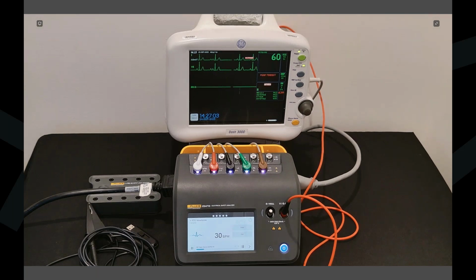One of the really cool features about doing this, if you wanted to set your limits, you could set a normal limit, a lower limit to set the alarms off on your monitor. You could reset it back to a normalized limit and then reset it back up to your high limits, capturing a full spectrum of testing all within one procedure. So here I see two things. I see my monitors displaying 30 beats a minute. I also see the audible alarms. So there's a pass.